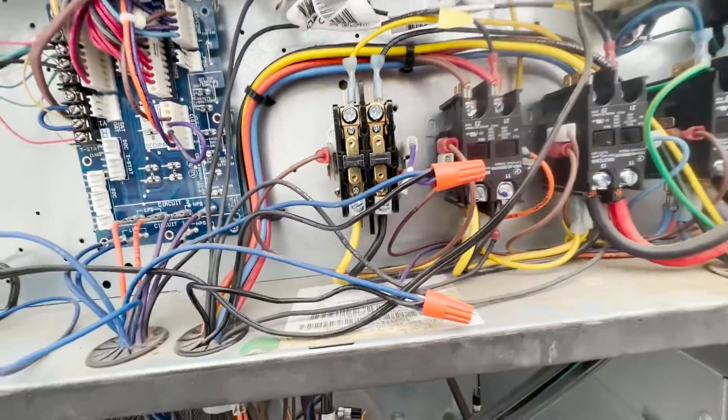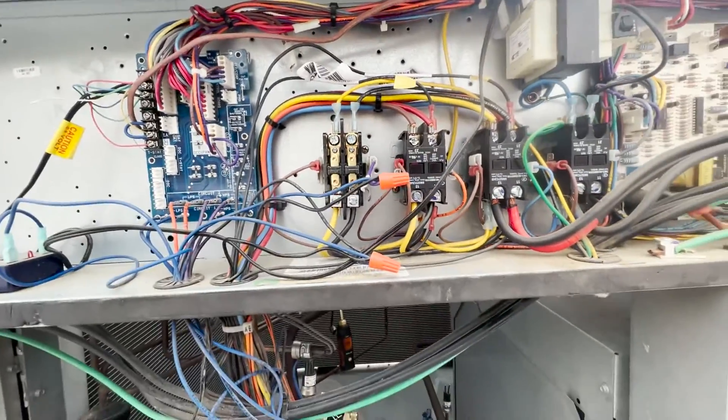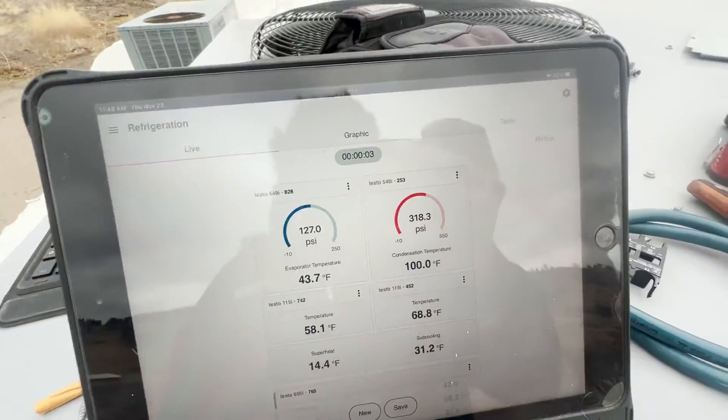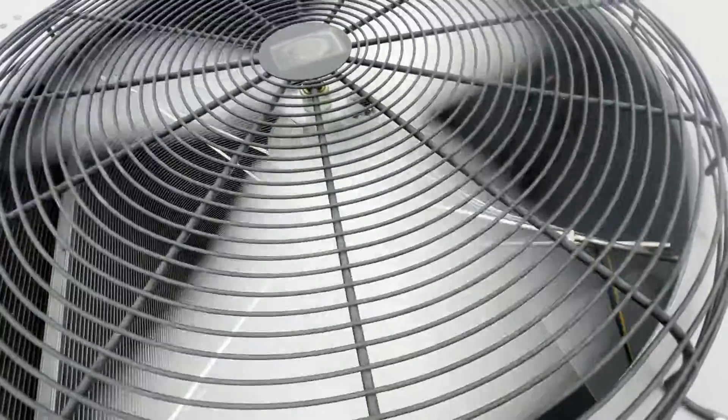There's a lot of room for upgrades — just leave it at that. New contactor's in. It pulled right in as soon as the pressure switch hit where it's supposed to hit, then kicked right out.